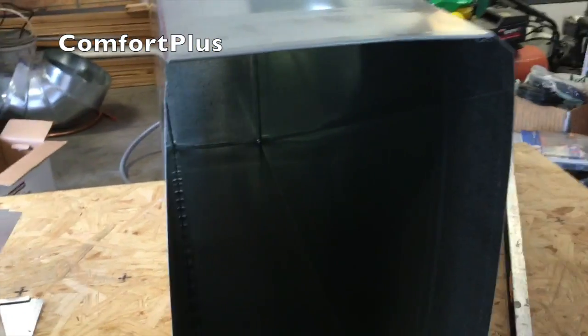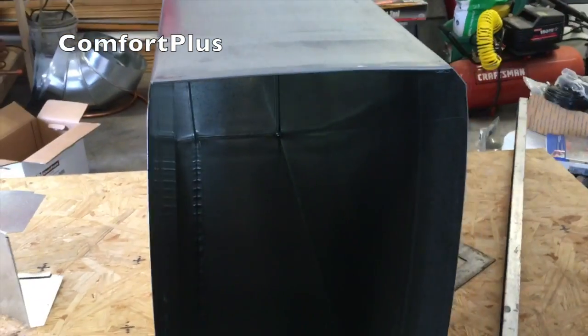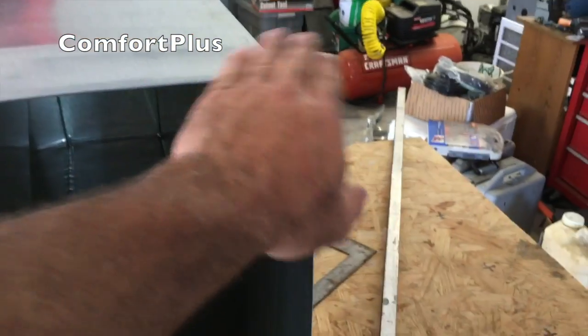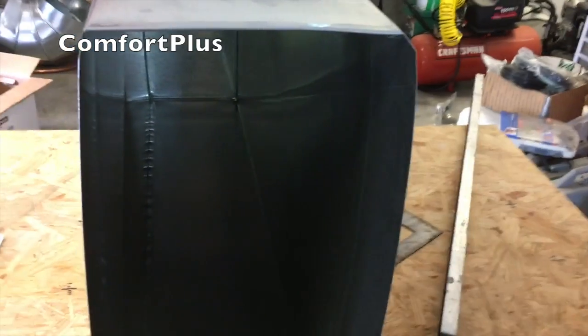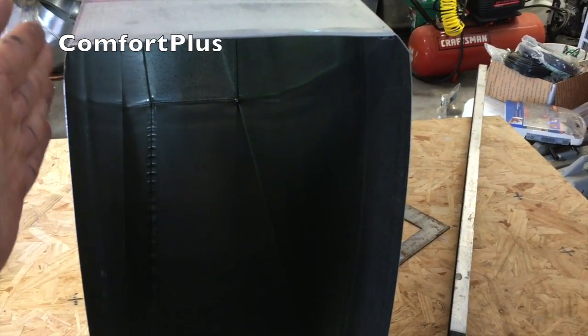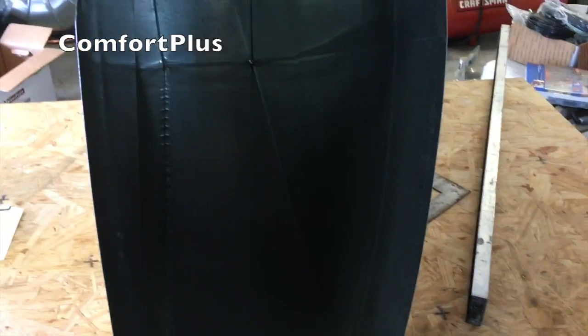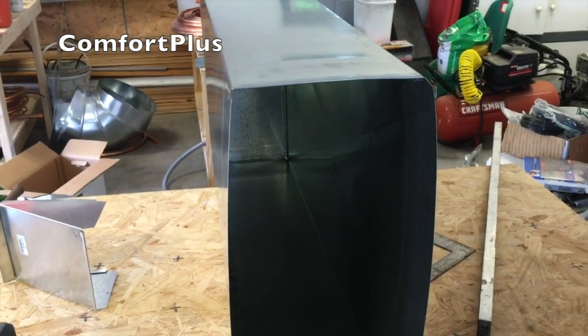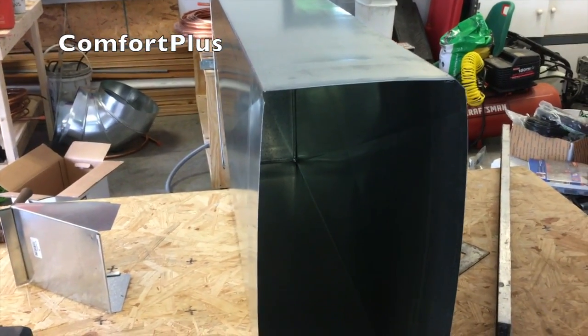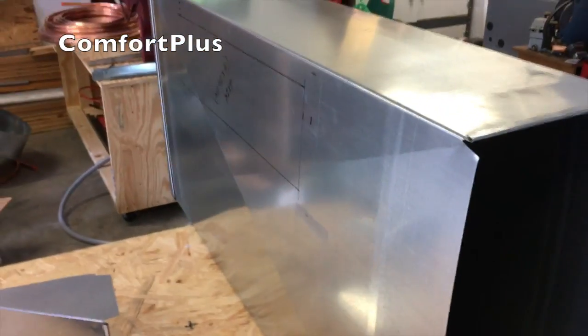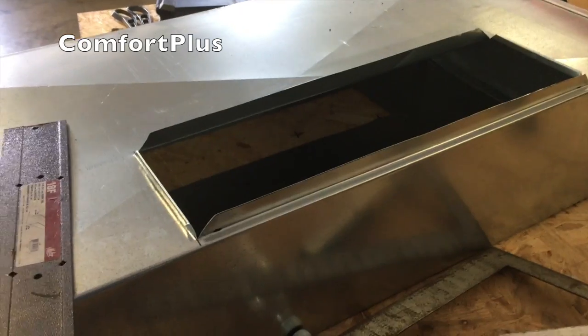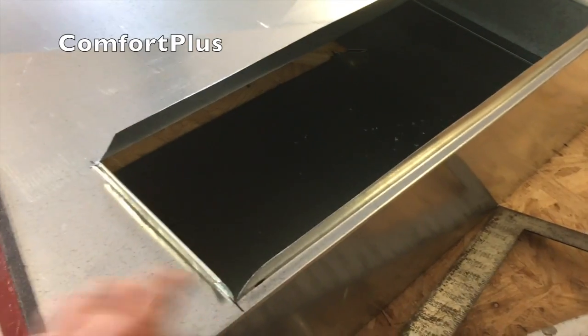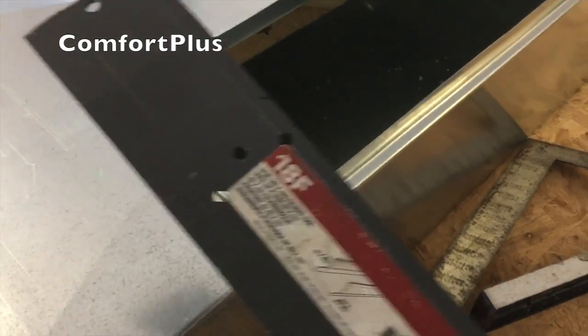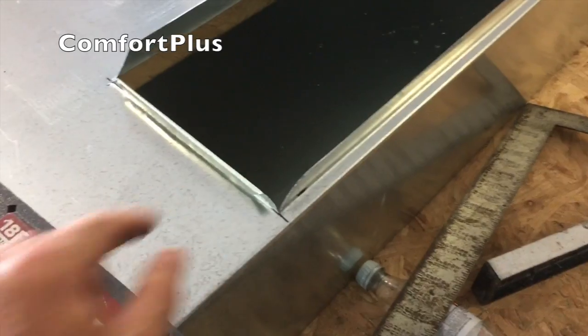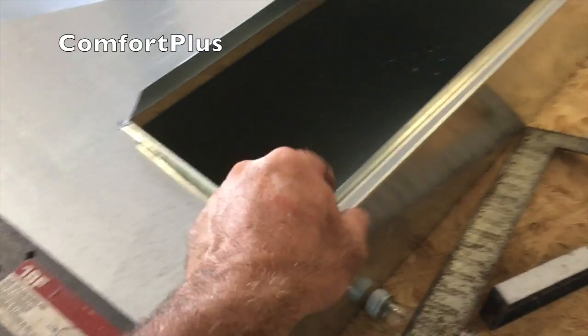What I'll probably do is line up the top and this side, which will be the back is the way I would call it if I was at the air handler. And so I'll make this be the common side, and then I'll make my transitions on the front and bottom so that it adapts to the air handler. And I'll do as much of that stuff up here as I can so I'm not fooling with it under the crawl space. And of course, once you get your hole cut, you can take a bending tool and bend for your drives and your S-locks.